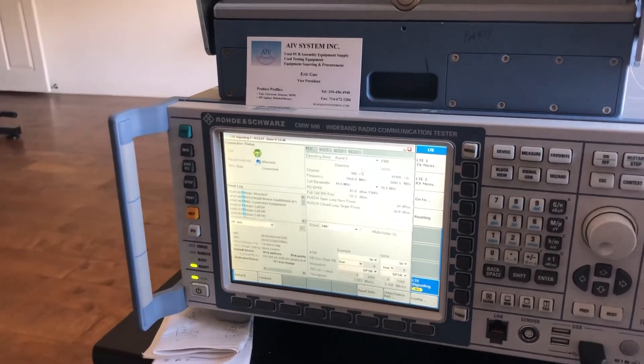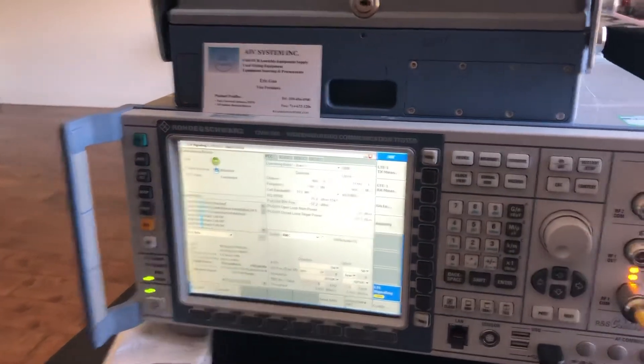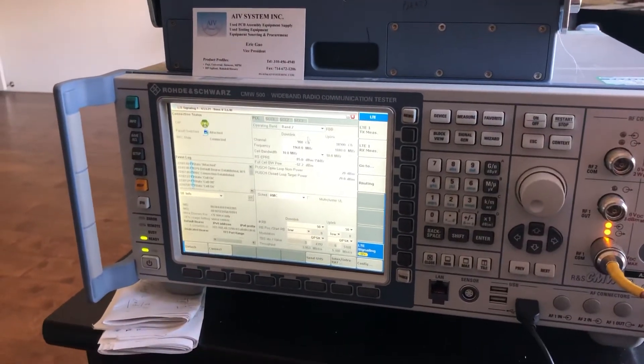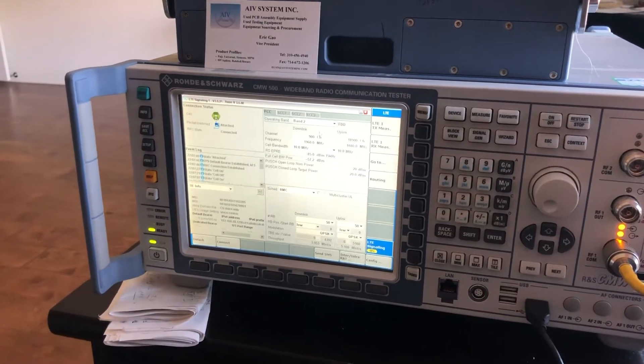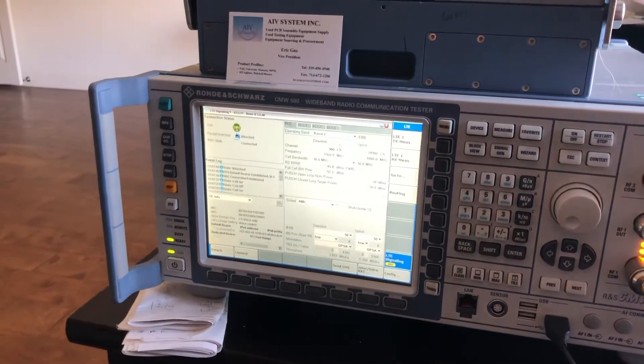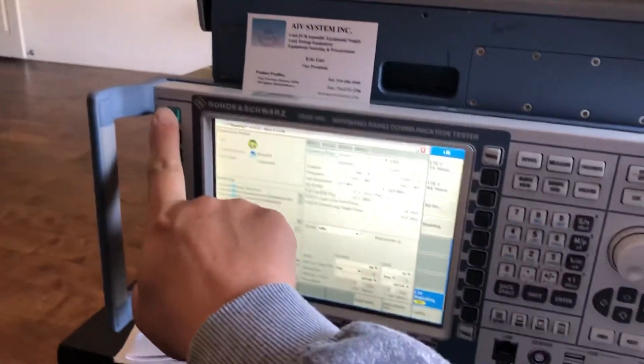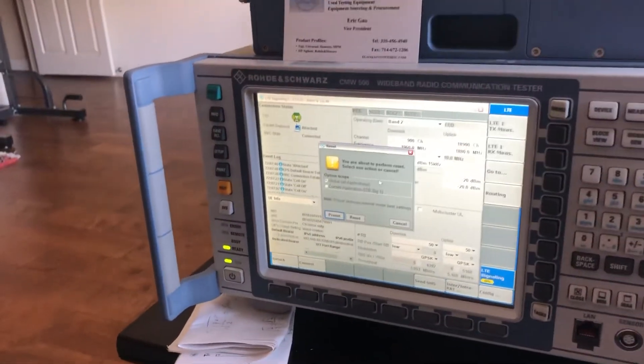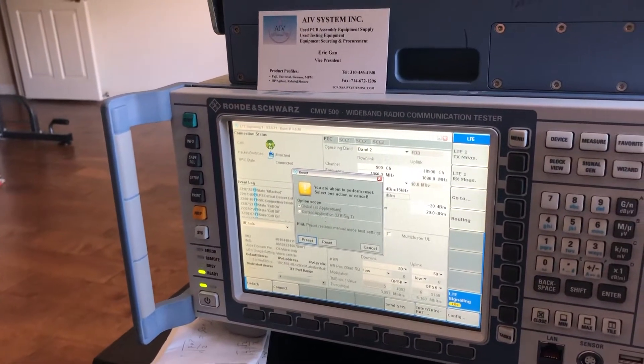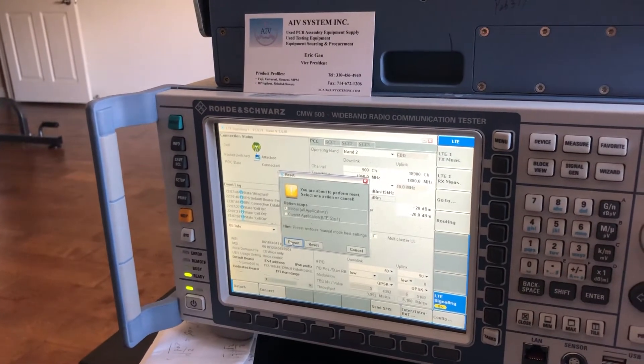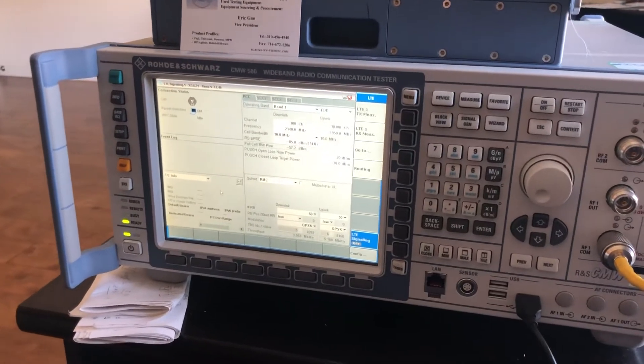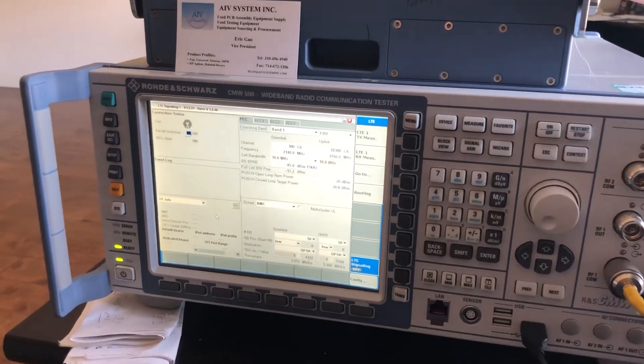I can show you how to connect to the device on the signaling mode. First, once you get this instrument, you don't know if somebody has used it before, so we just go reset. Go to preset, preset all global applications.